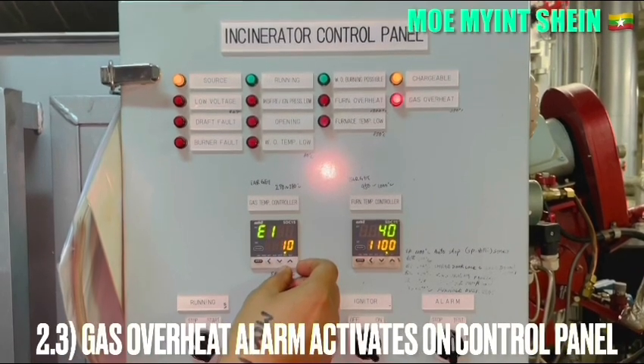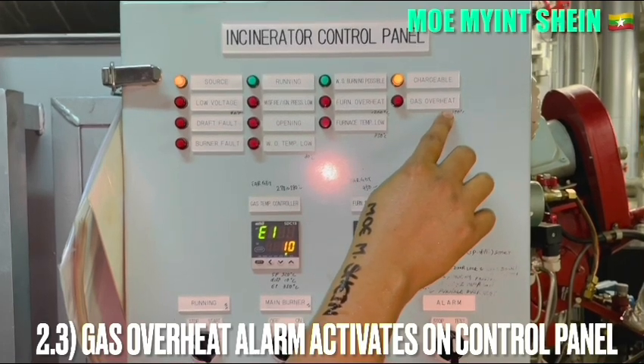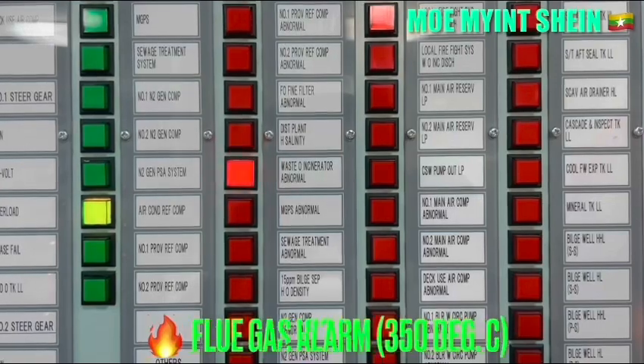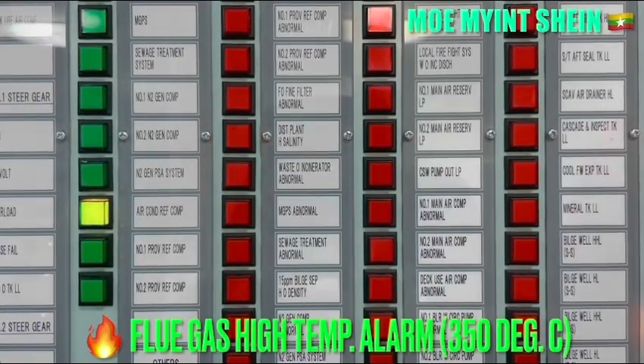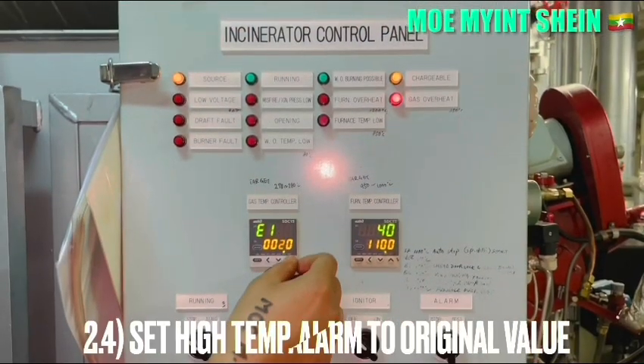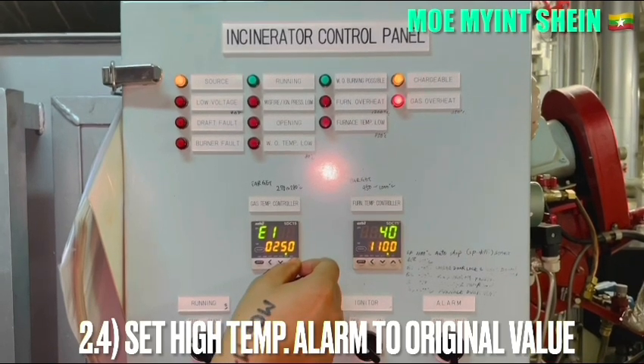The flue gas high temperature alarm activates on the control panel after a few seconds. The flue gas high temperature alarm is set at 350 degrees centigrade. After the test, set the high temperature alarm back to the original set value of 250 degrees centigrade.